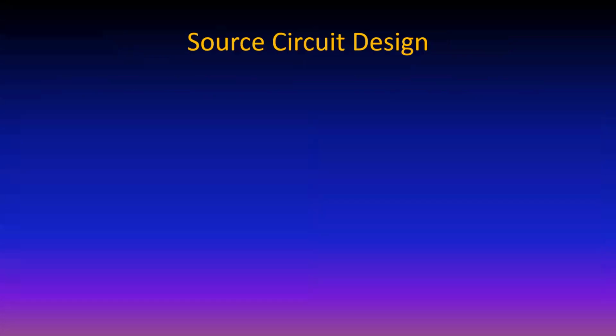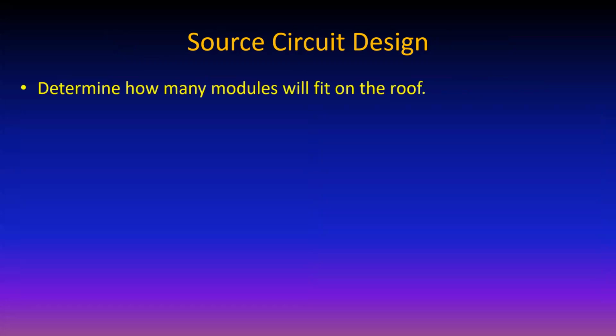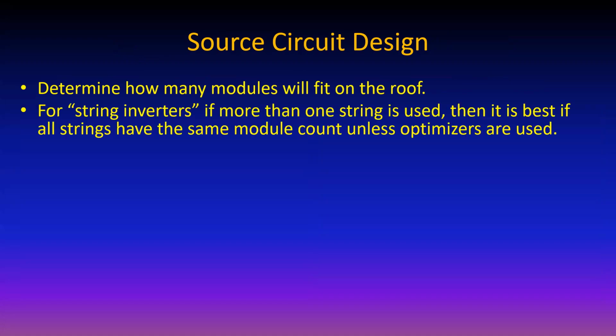So let's go to a source circuit, which is the connection of the leads of the modules that will connect in series for a string circuit, okay? And so first of all, we determine how many modules fit on the roof. We already did that. We can fit 14.